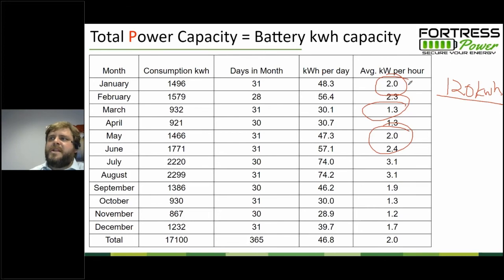And then for the month of January, every hour I'm subtracting 2 kilowatt hours, and then I'm adding back in what PV Watts tells me I should be up to a maximum of what my guess was. I guess the battery bank should be 120 kilowatt hours at midnight and at 1 a.m. and at 2 a.m. and at 3 a.m. I'm subtracting out 2 kilowatts per hour, and then when my PV Watts data shows the sun coming back up, I'm adding that back in until my battery is fully recharged.